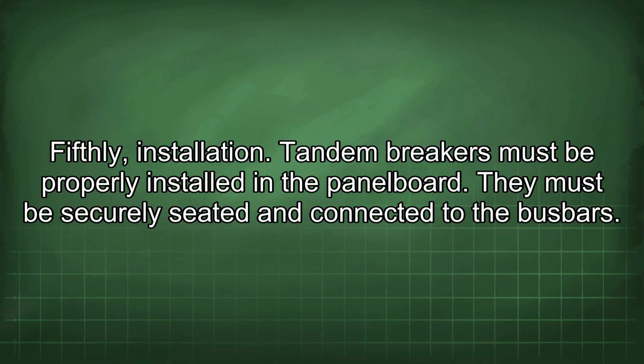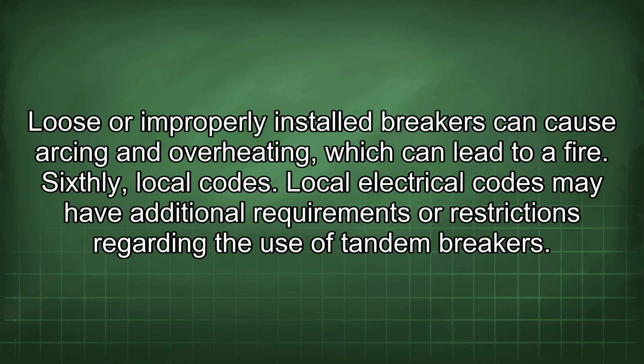Fifthly, installation. Tandem breakers must be properly installed in the panel board. They must be securely seated and connected to the bus bars. Loose or improperly installed breakers can cause arcing and overheating, which can lead to a fire.